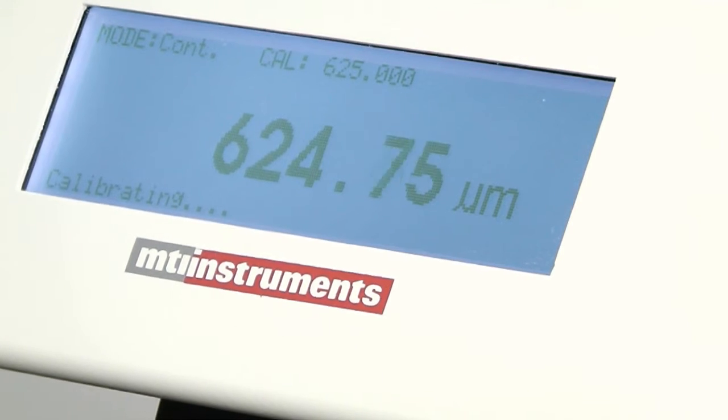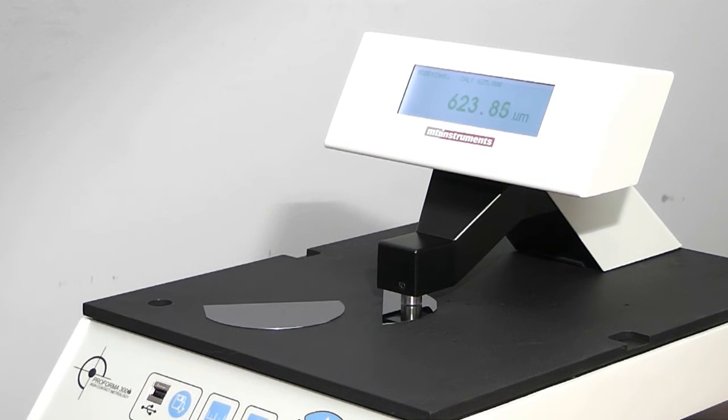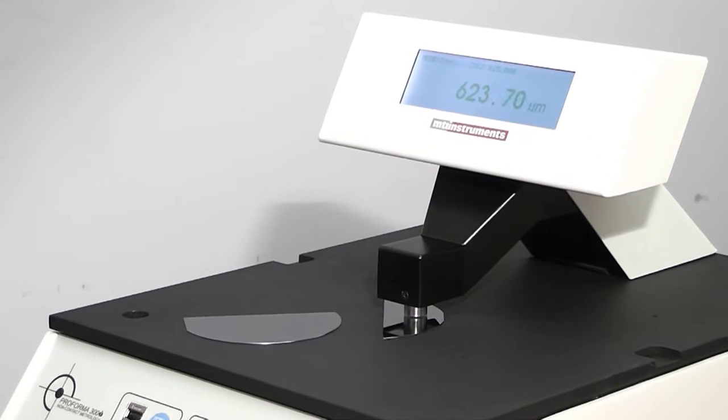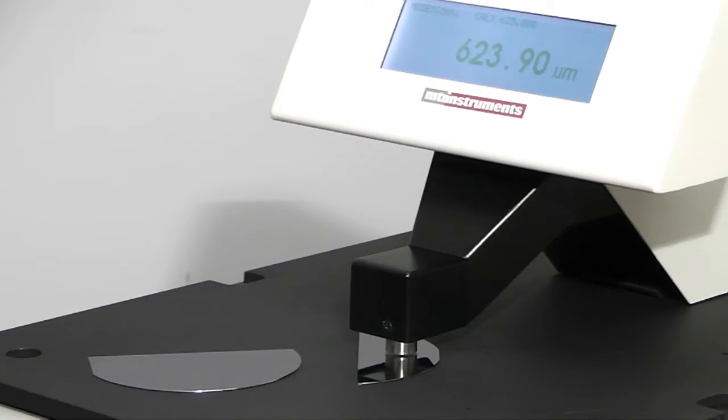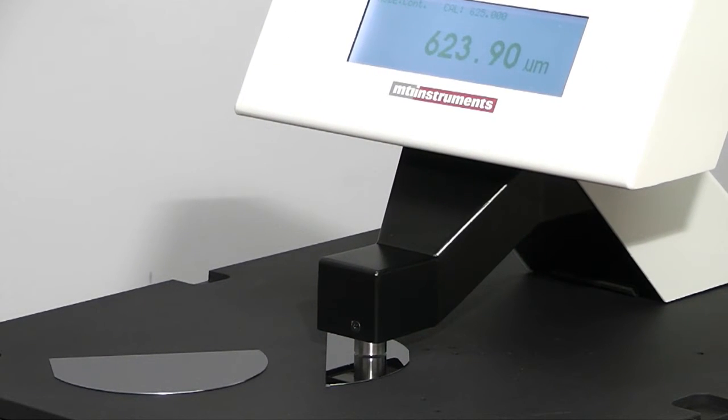All right. So now we're reading 625 microns. We'll take a quick look at the other side of this sample that is broken off, and we can see that we're reading 600 and 24 microns, okay? So it's the sister piece, same process, so they should read the same. And that's how you would set up to do a calibration with an insulating wafer.